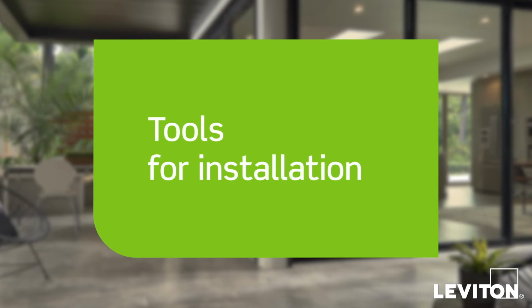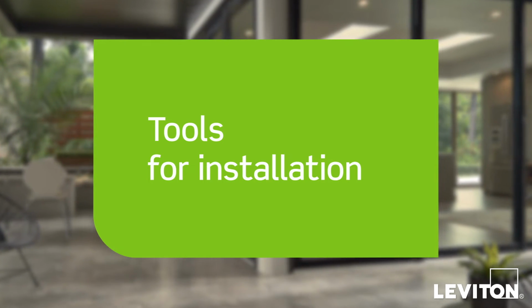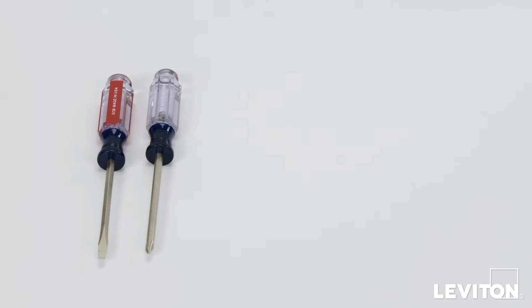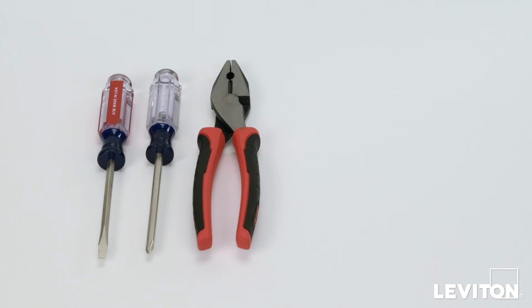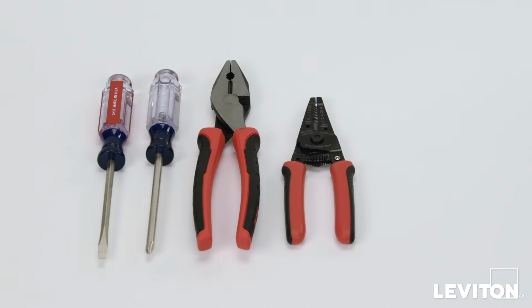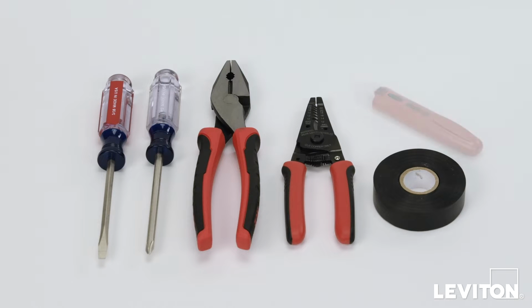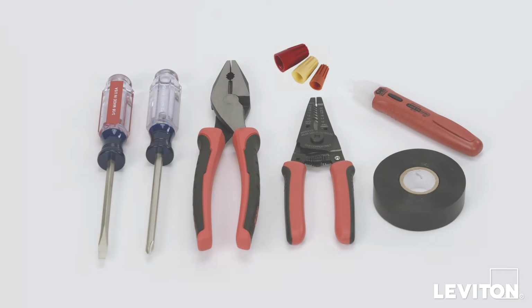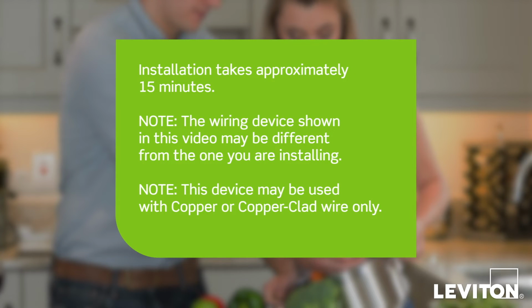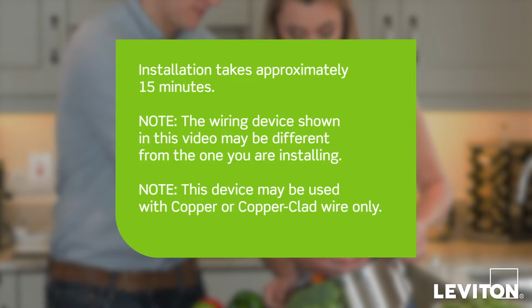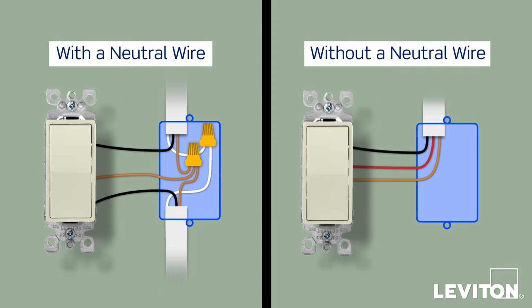When installing and terminating this Leviton device, have the following tools on hand: a flathead screwdriver, a Phillips head screwdriver, electrician's pliers, a wire stripper, electrical tape, a handheld voltage tester, and properly sized wire connectors. Installation takes approximately 15 minutes. The process shown follows general guidelines. Local codes take precedence. These sensors require a neutral wire for installation.